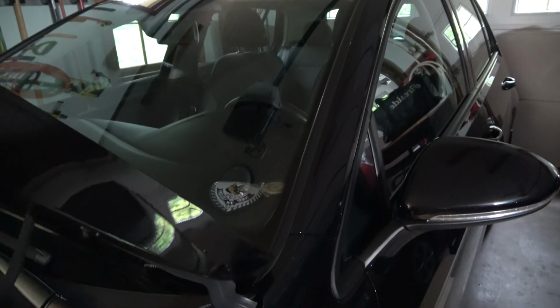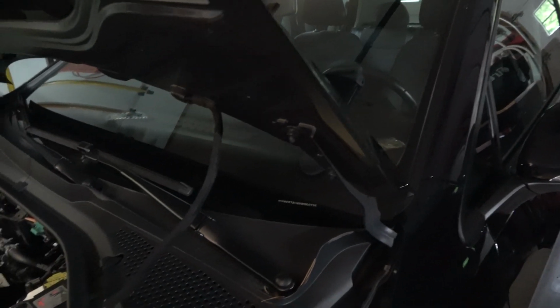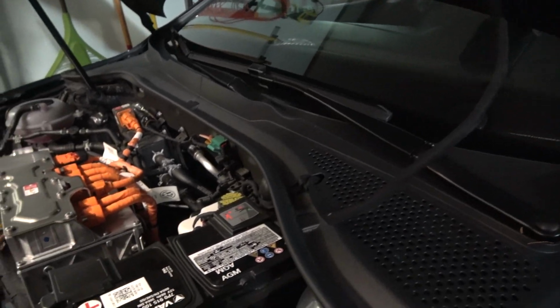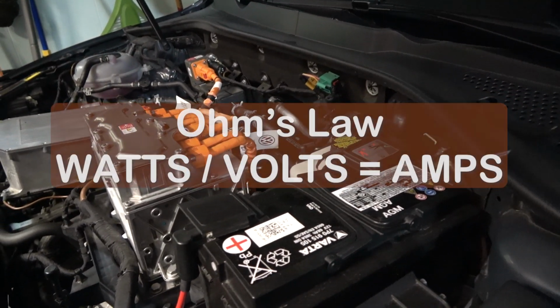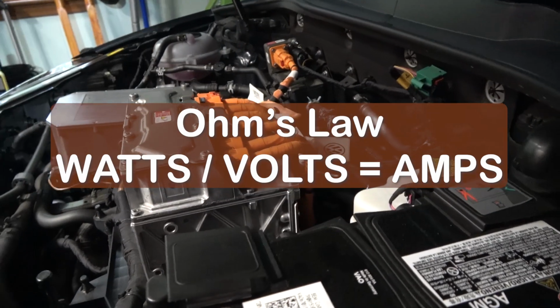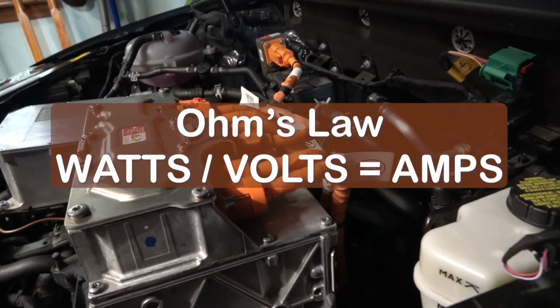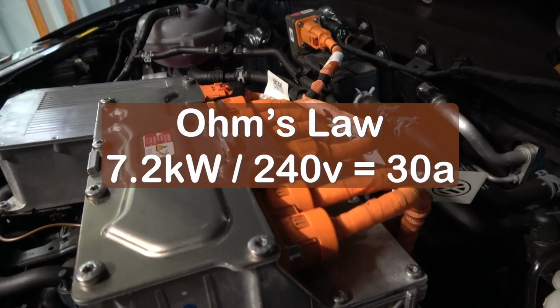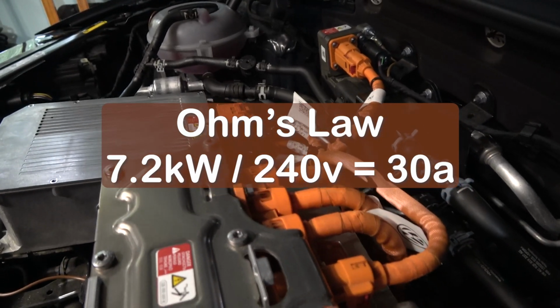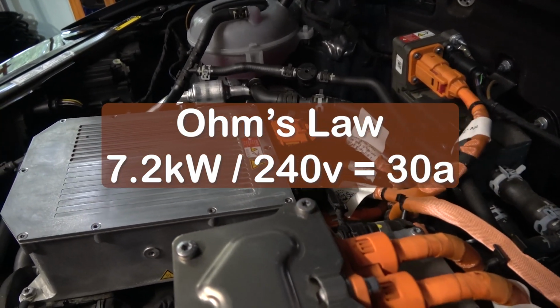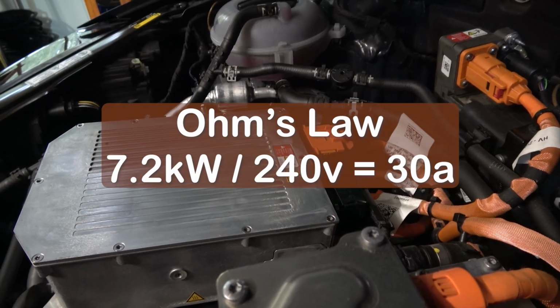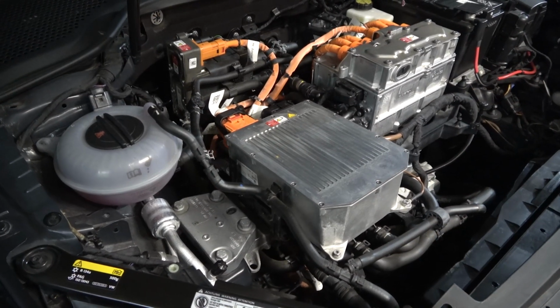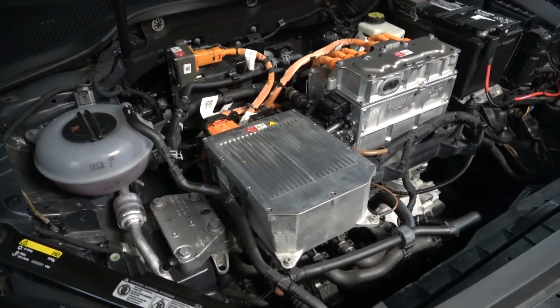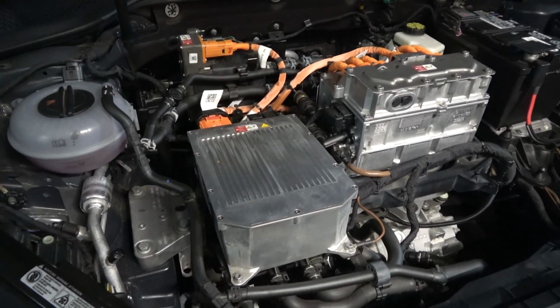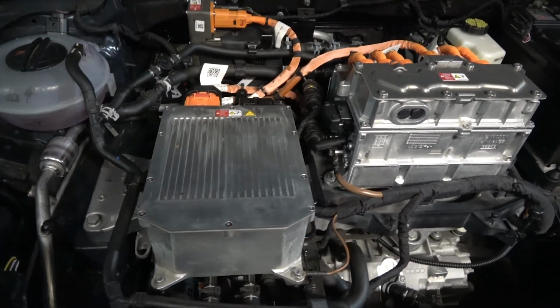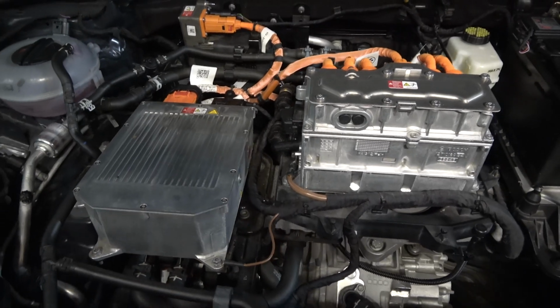My first step was to determine the maximum current the onboard e-Golf charger could use for level 2. By using Ohm's law, that's watts divided by voltage equals amps, I was able to determine that the onboard 7.2 kilowatt charger divided by 240 volts equals 30 amps. I also wanted to have some extra capacity so that if I decided to upgrade to an EV with a larger onboard charger, I could do so. I figured 40 amps would be sufficient.